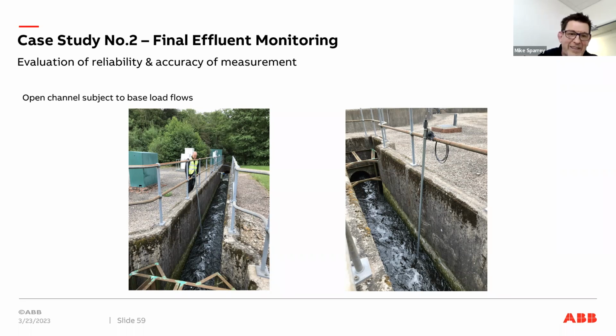It's not easy to see here, but this chamber can be quite flat. It's a base load system, so depending on the weather and what's being flushed down the toilets, the velocity of the flow can change very quickly, and the depths can change too. Typically it's quite a low level flow, and with our sensor we have to have it at least 30 centimeters below the level of the water, otherwise light will get to the optics and cause problems. It also has to be a minimum of 5 centimeters away from any surfaces, i.e. the sides or the bottom.